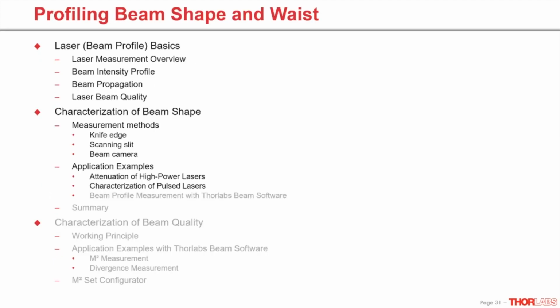Next, I would like to say a few words about the measurement of pulsed lasers, since most material processing lasers fall under this category. For laser measurement with a high repetition rate, the measurement equipment works in a quasi-continuous wave operation. You don't have to care about anything.